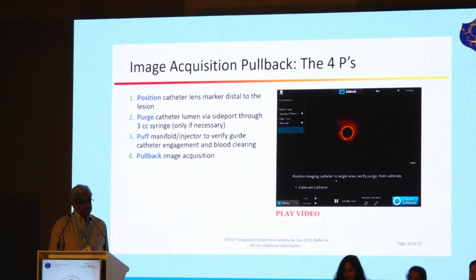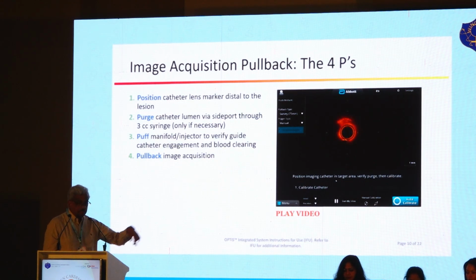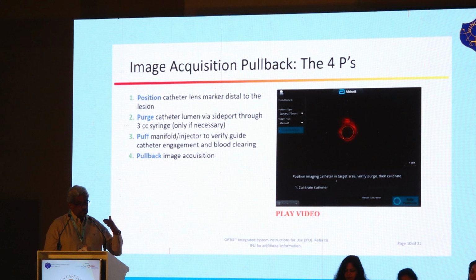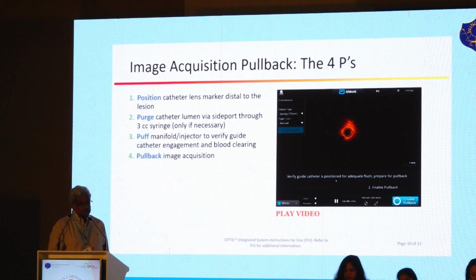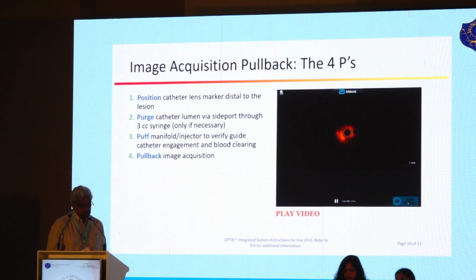And then you position your catheter lens distal to the lesion. Purge the catheter lumen via the side port. There's a side port on the catheter. We use a 3 cc syringe, and be very clear that the dye is clearing through the whole thing. Puff the manifold to verify guide catheter engagement and blood clearing, and then pull back the image.